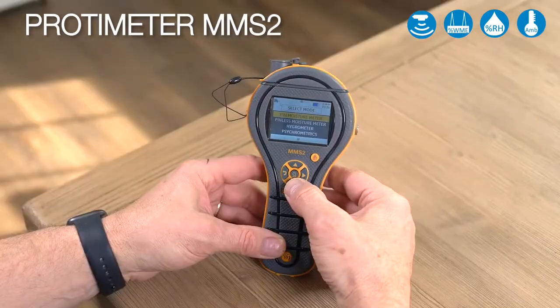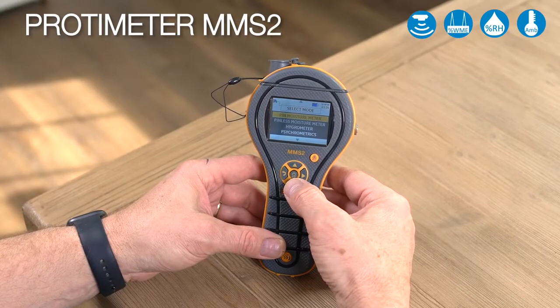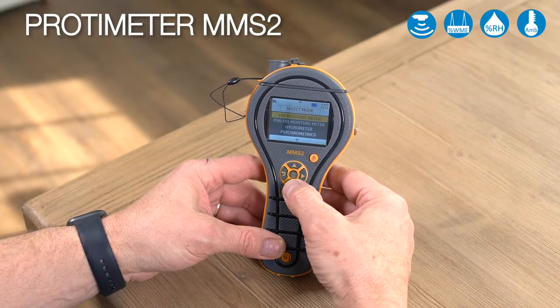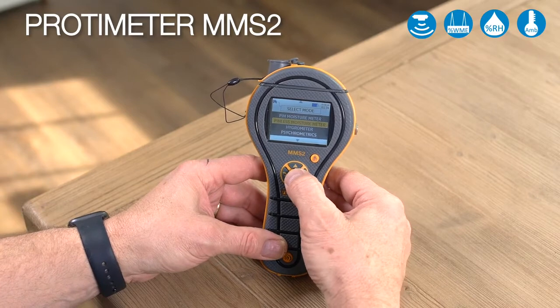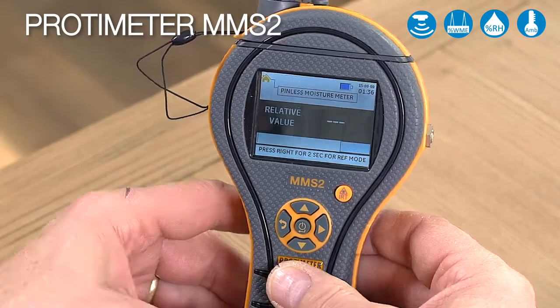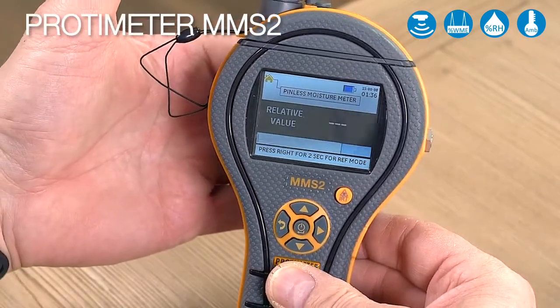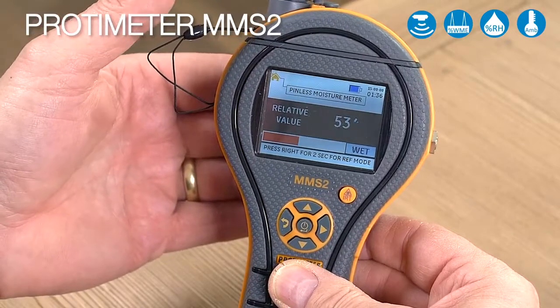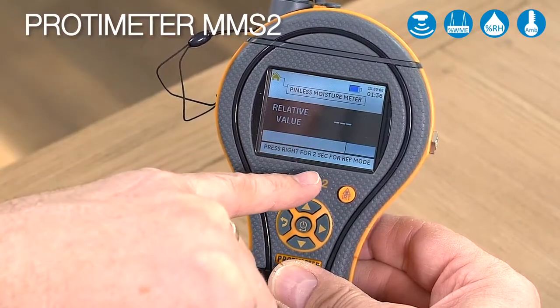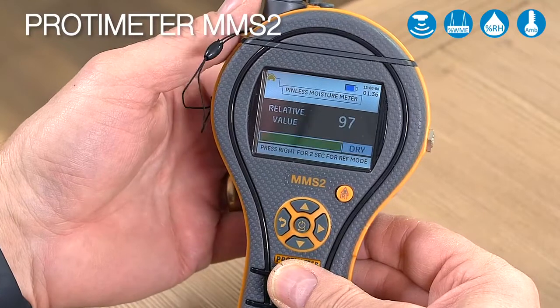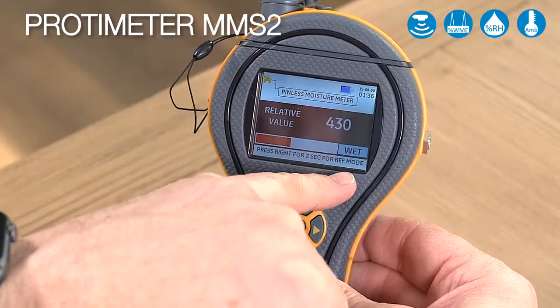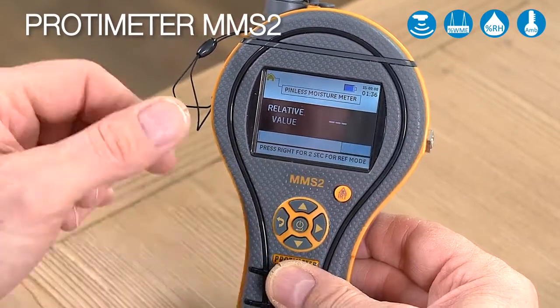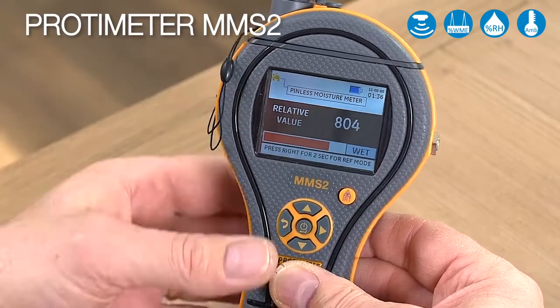Now let's look at the pinless moisture measurement mode, also called non-invasive. We push the arrow down once, press enter, and now we're in the pinless mode here. This is giving us readings from the back. Again, you can see the green, yellow and red as well as the reference reading there. It also, just like in the pin mode, says wet, at risk and dry.